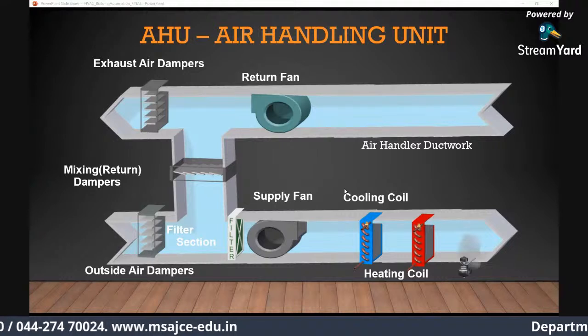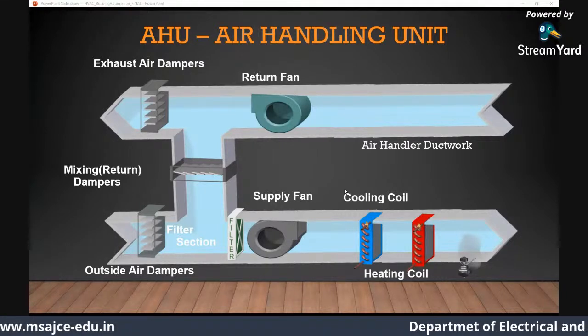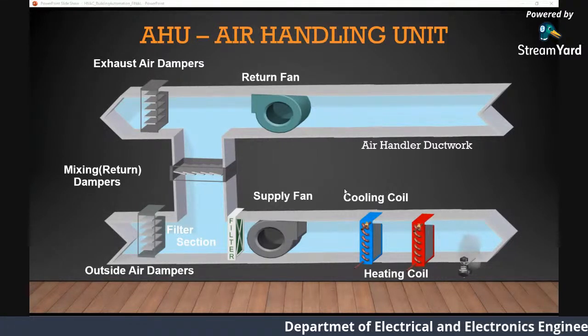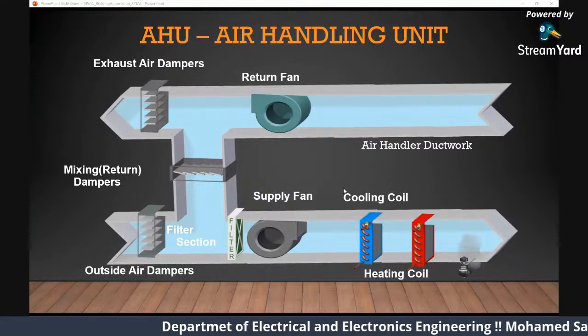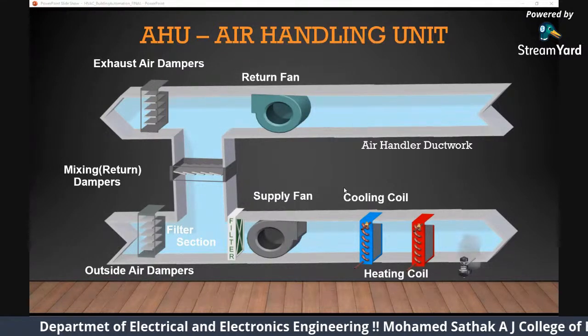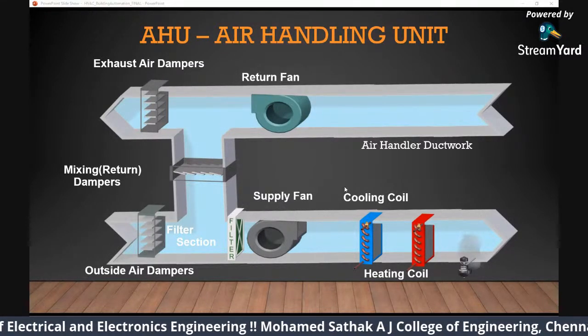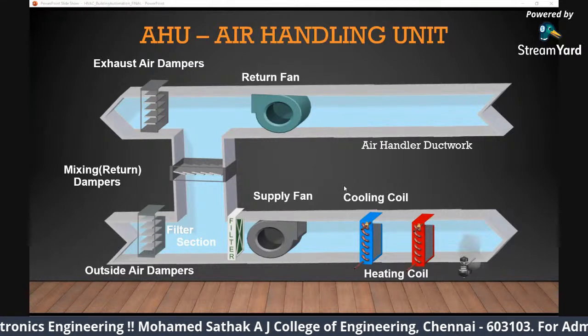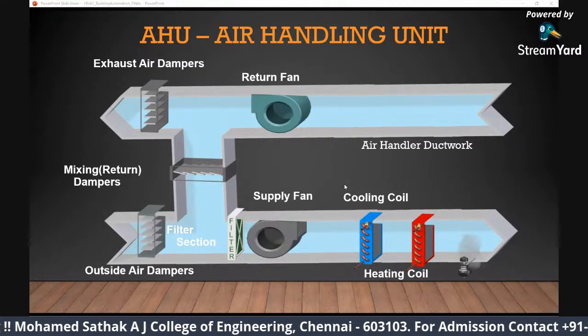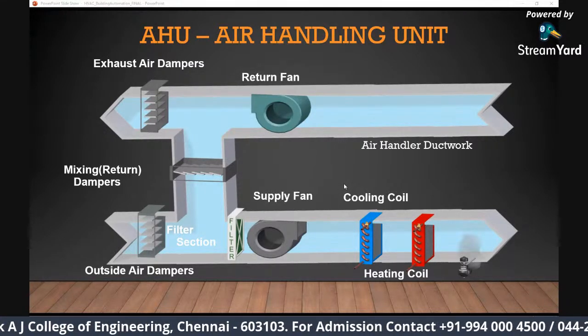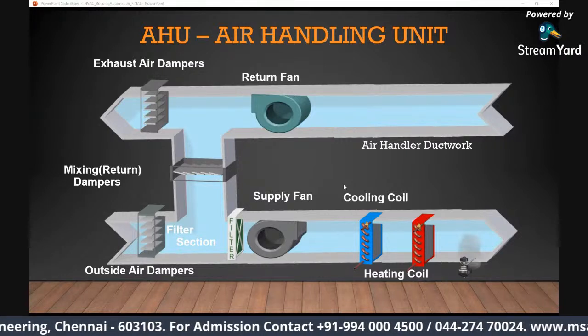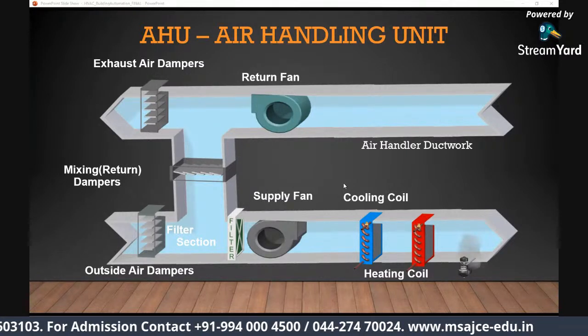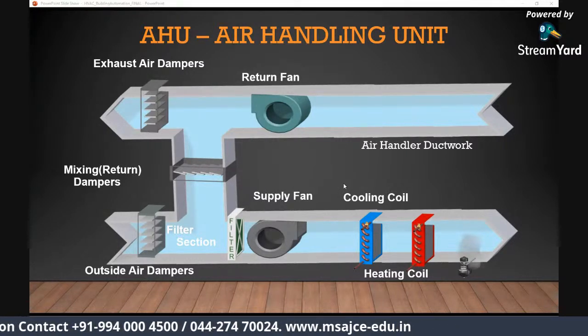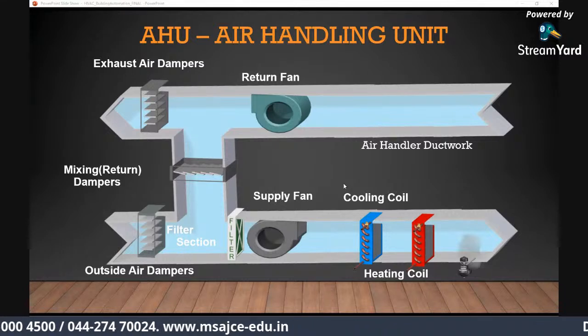Okay. So you can see other components like dampers. Dampers are a very important component of an AHU. You can consider them as navigators. Consider them as windows in your house. There is a fan operating and there's a window before it. Only when you open the window will the outside air come in, or the inside air rotate. So the outside air damper is to get the outside air into the building. Your return air damper, as you can see, is to circulate the air inside the building.